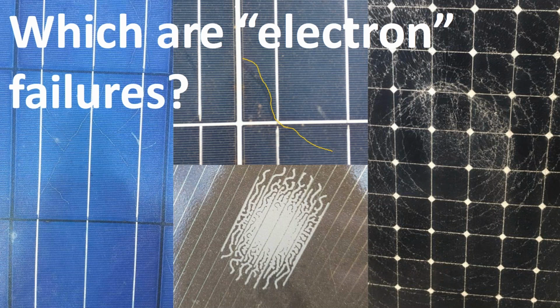But these are breaches in the cell where electrons have started to short circuit within the cell themselves, and the cell structure starts to kind of rip apart. So these snail trails, to some extent, are inevitable.